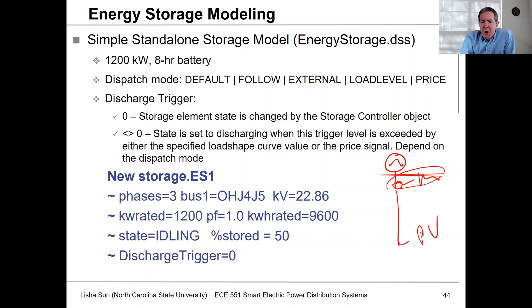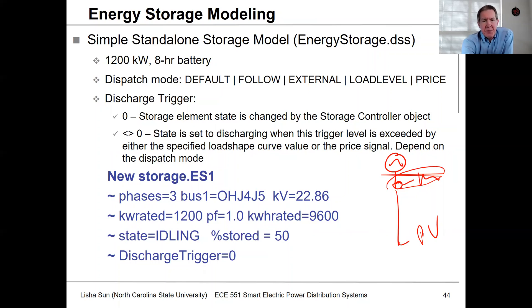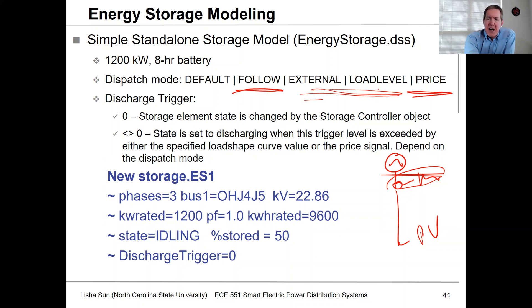Energy storage is probably one of the less mature models in OpenDSS — it hasn't been in there that long. Like EPRI, they develop capability as needed for projects, but it may not have all the functionality you'd want. There are a lot of different dispatch modes: you can follow a load curve, follow commands, set up peak shaving, or have it operate on a price signal.